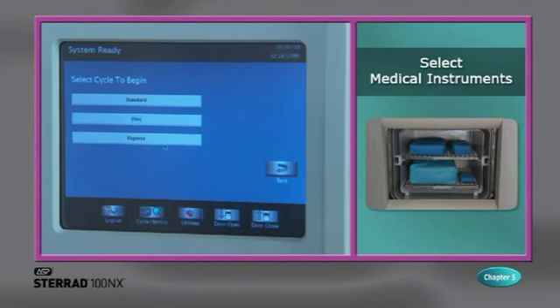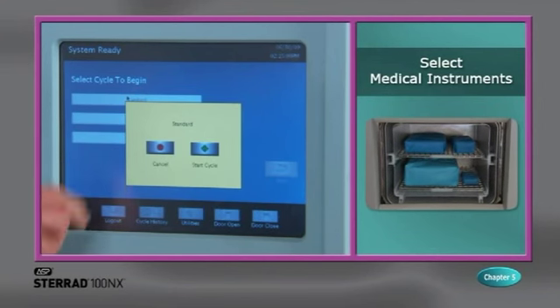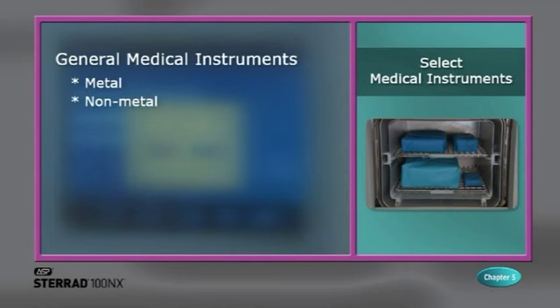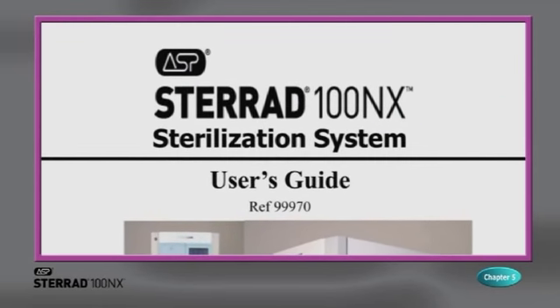The standard cycle is 47 minutes and should be selected for instruments that meet the following criteria. General medical instruments, metal and non-metal, including hinged devices. Instruments with single-channel stainless steel lumens, internal diameter 0.7 millimeters or larger, and length 500 millimeters or shorter. Reference What Can I Sterilize in the Sterrad 100NX system, which is located in the user's guide. Polyethylene and Teflon lumen tubing with an internal diameter of 1 millimeter or larger and length of 1,000 millimeters or shorter. These items must be sterilized without any additional load items. Limit of 20 pieces of tubing per cycle.